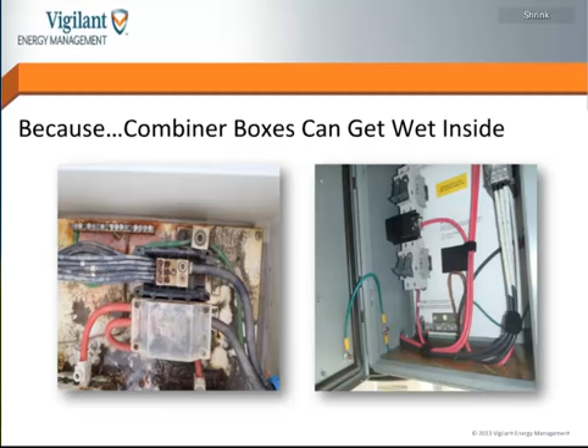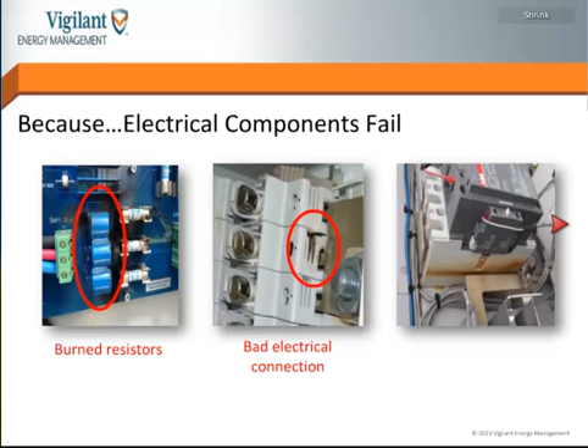And why O&M? Also because we get electrical component failures. This first picture to the left had the resistors on this board burned out, so that caused the failure. The second picture is of fuse holders, and if you look there close, you can see that one of the fuse holders started to melt and burn, and that was just because the set screw wasn't tightened down on the tooth of that bus bar. It was a loose connection. It actually came from the factory that way, and we didn't notice this until after several months of it being in operation, and we saw this with our thermographic imaging camera.